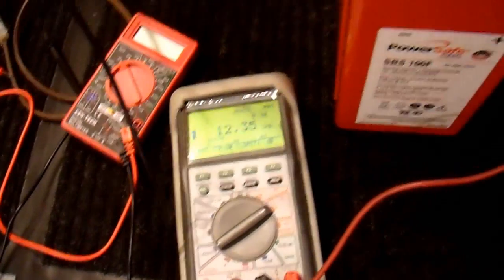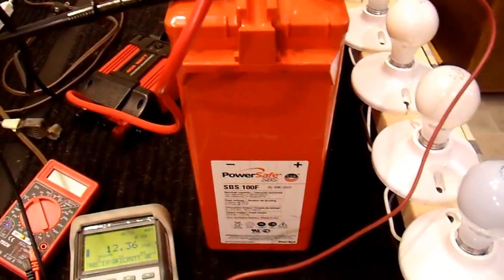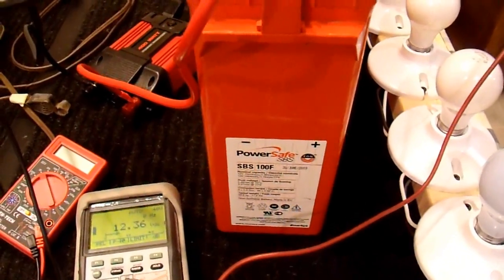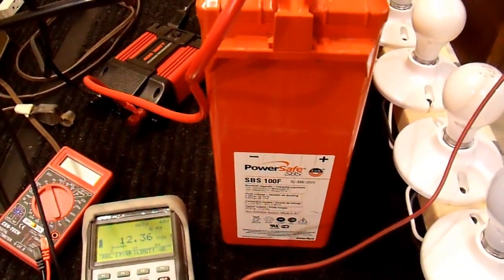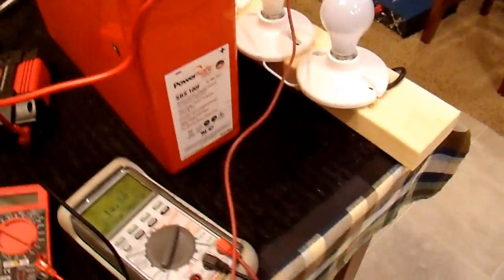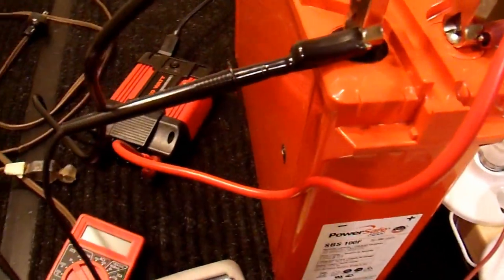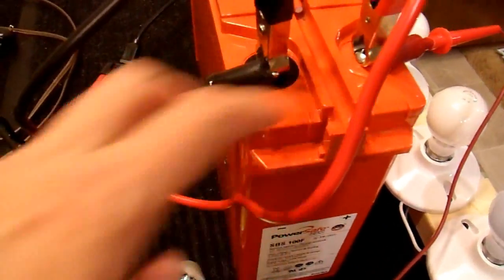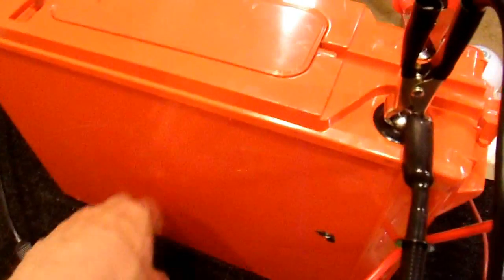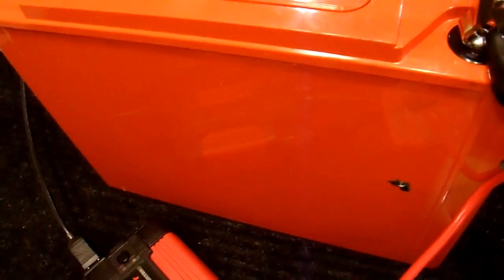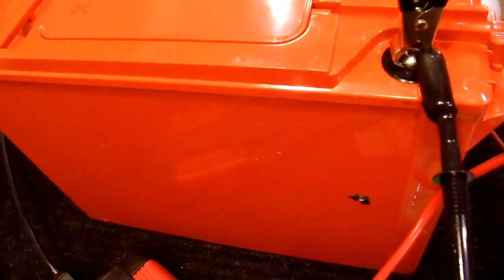And that's because this battery still has a significant amount of capacity remaining. The real issue here isn't that the battery is drained. It's that the internal resistance is high enough that it can no longer support a 20 amp load. So the internal resistance is high enough that it gets enough voltage drop primarily in this one cell that got warm that my voltage at the terminals is 11 volts. So we're probably getting a volt voltage drop or more just in that one cell and that's not good.